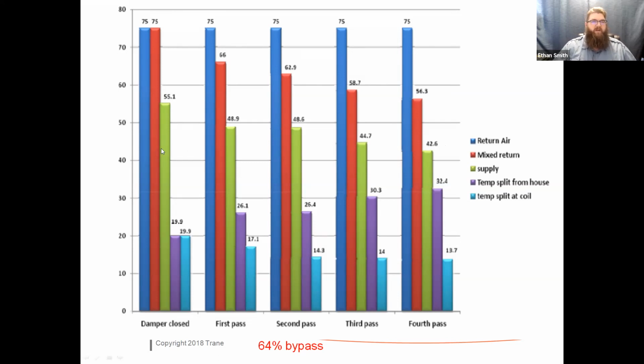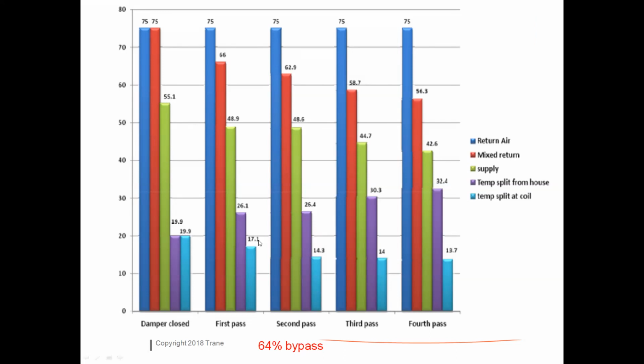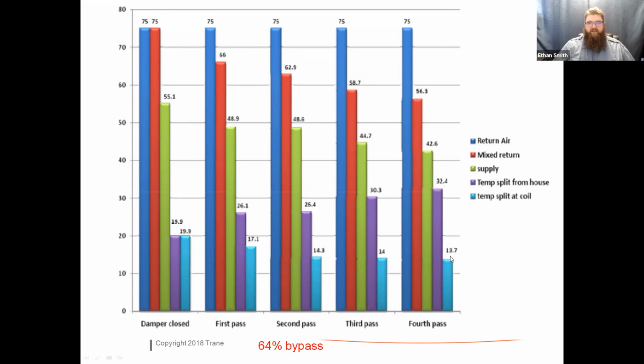My coil temperature is probably around 35, 36 degrees when I'm getting a 55-degree discharge. So I'm freezing the coil now. You can see that my capacity for my indoor coil is steadily dropping. I'm only getting a 13-degree split across the indoor coil, but I'm delivering a 32-degree split at the registers because of that mixed air. At the register, we're still pulling in 75-degree air, but we're discharging 42-degree air.